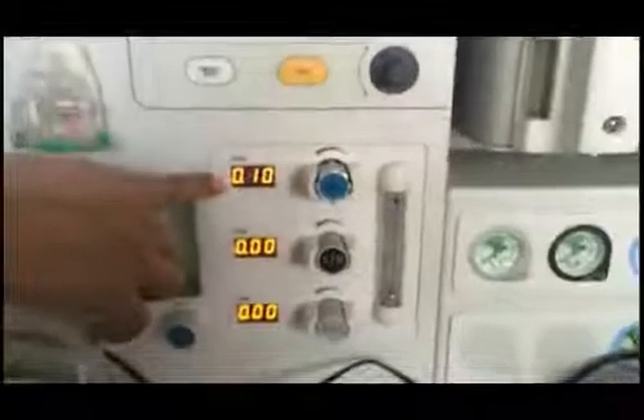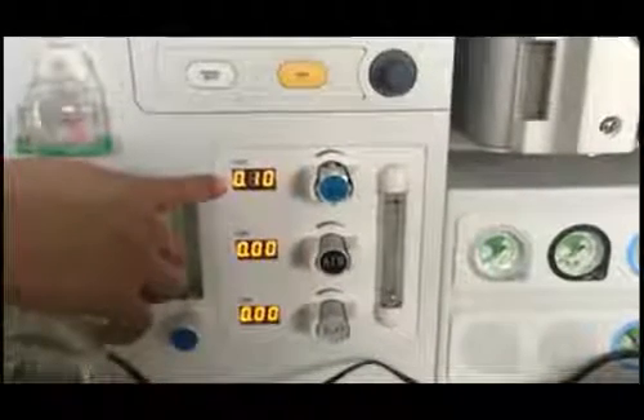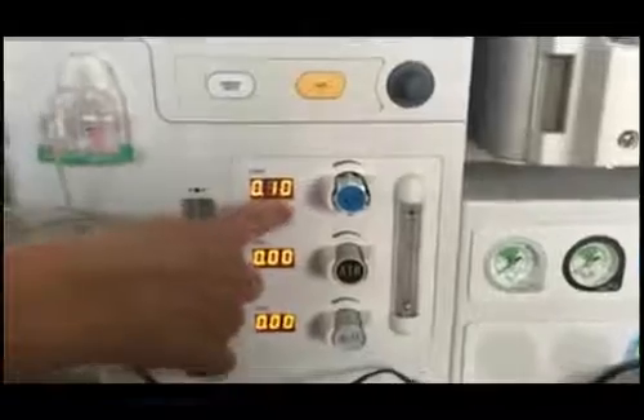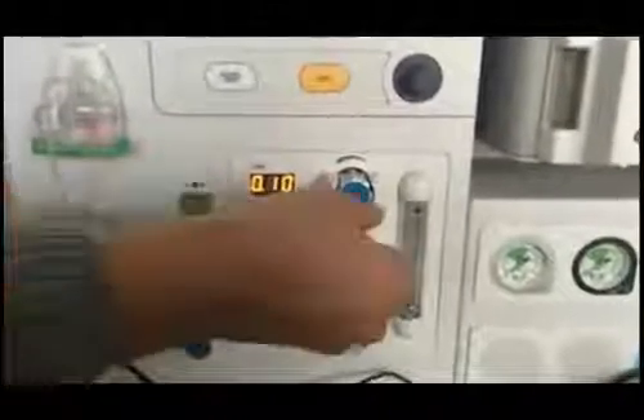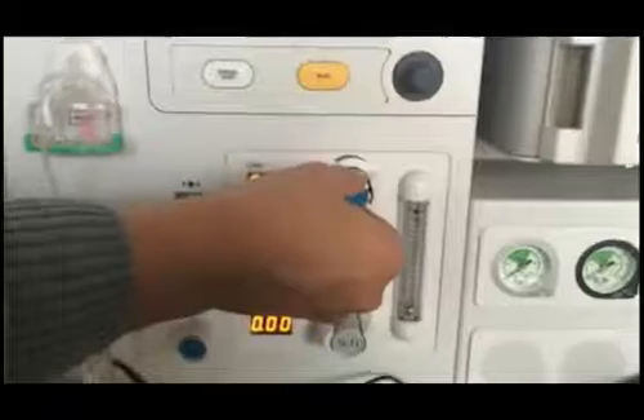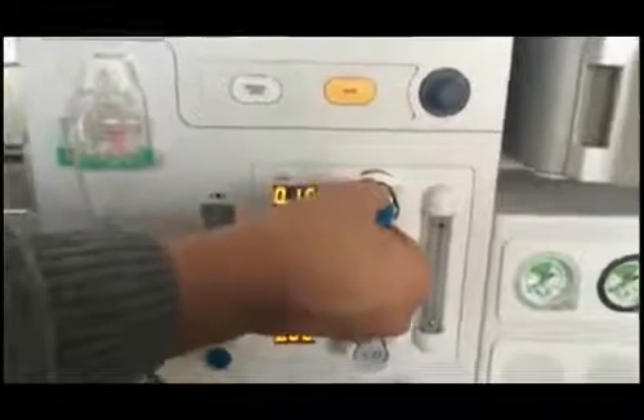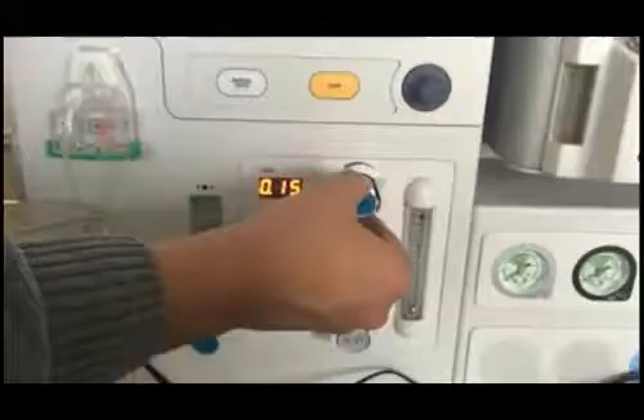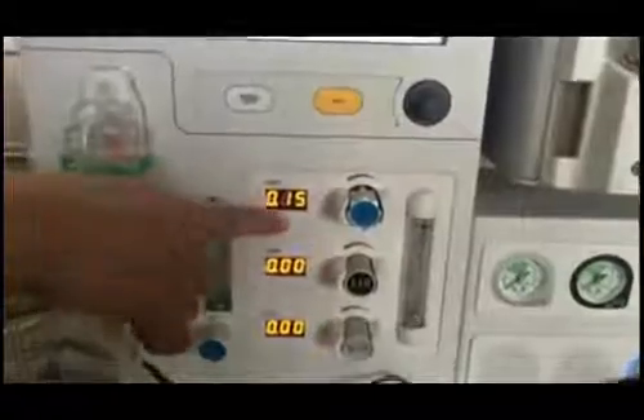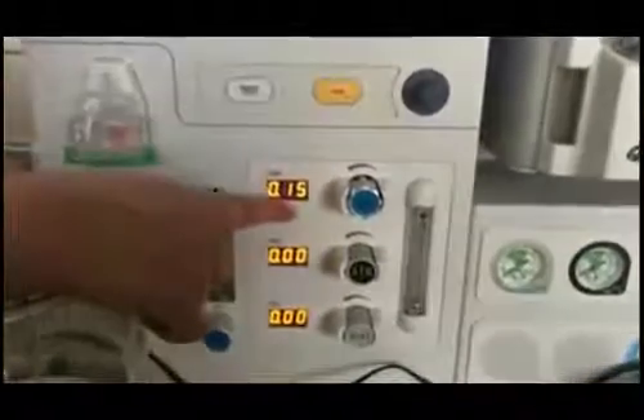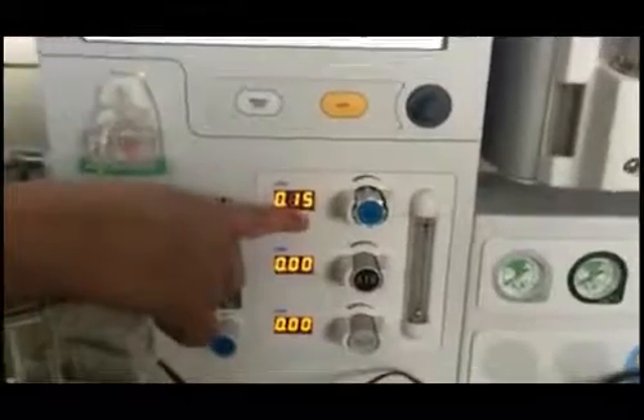Now I will set the flow meter to 150 milliliter per minute. This is the flow meter. This is 0.10. This means 100 milliliter. This is 15, but this corresponds to 150 milliliter. After setting this, I will press the start button to perform the calibration.